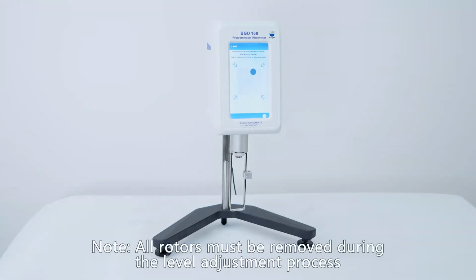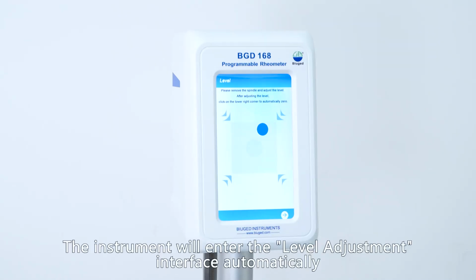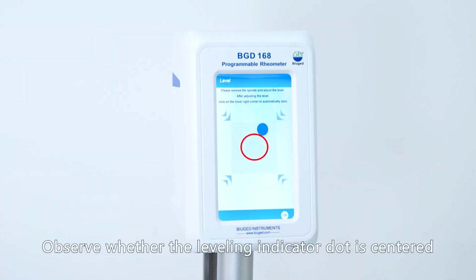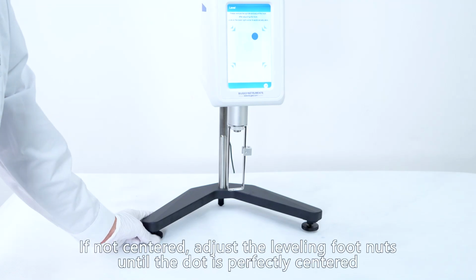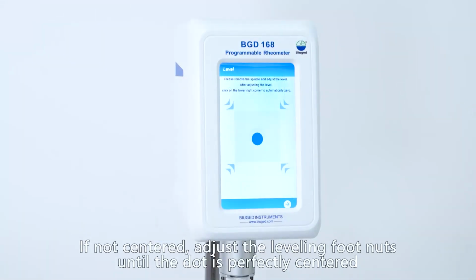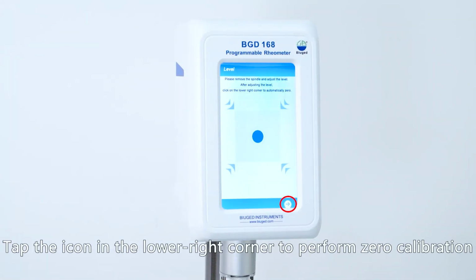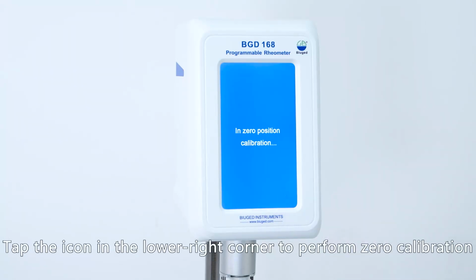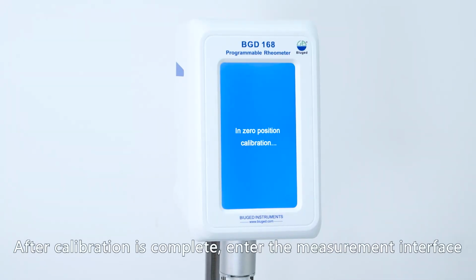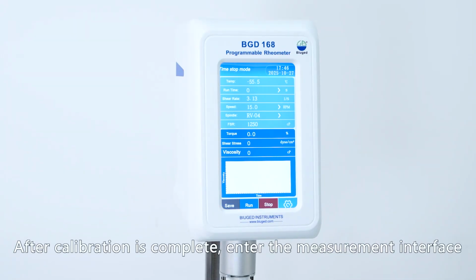Note, all rotors must be removed during the level adjustment process. The instrument will enter the level adjustment interface automatically. Observe whether the leveling indicator dot is centered. If not centered, adjust the leveling foot nuts until the dot is perfectly centered. Tap the icon in the lower right corner to perform zero calibration. After calibration is complete, enter the measurement interface.